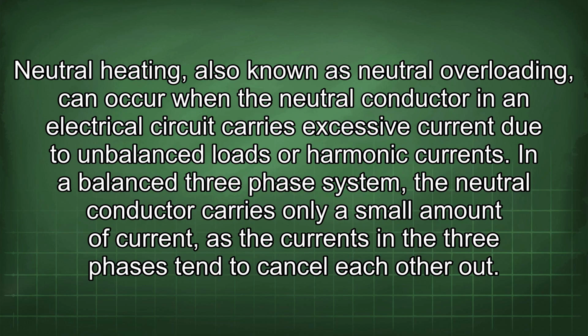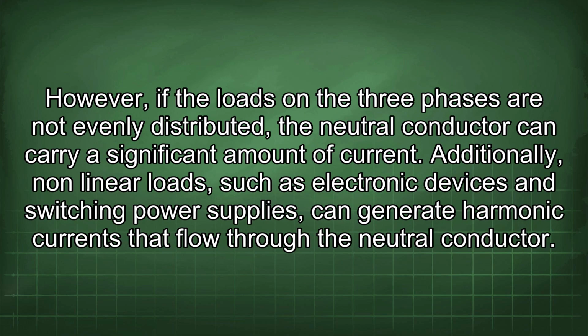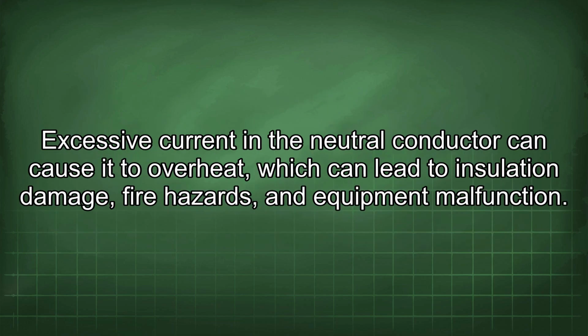Neutral heating, also known as neutral overloading, can occur when the neutral conductor in an electrical circuit carries excessive current due to unbalanced loads or harmonic currents. In a balanced 3-phase system, the neutral conductor carries only a small amount of current, as the currents in the three phases tend to cancel each other out. However, if the loads in the three phases are not evenly distributed, the neutral conductor can carry a significant amount of current. Additionally, nonlinear loads, such as electronic devices and switching power supplies, can generate harmonic currents that flow through the neutral conductor. Excessive current in the neutral conductor can cause it to overheat, which can lead to insulation damage, fire hazards, and equipment malfunction.